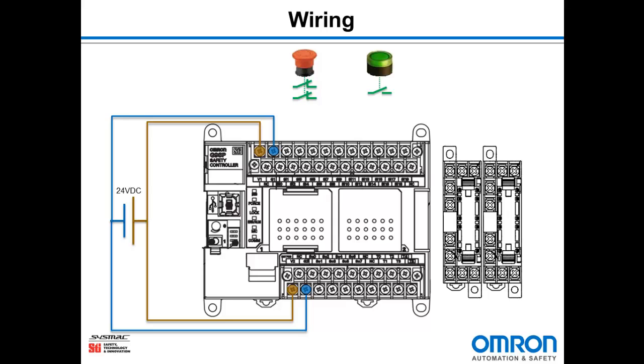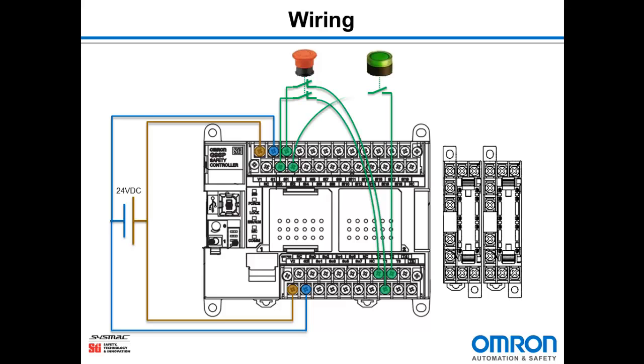Next we need to wire our inputs. I'm going to take the test output signal T0 through the first contact of the e-stop switch and back into safety input 0. Test output 1 will go through the other contact and back into safety input 1. Now I need to wire the reset button. It's going to go through test output 2 and then back into safety input 2.